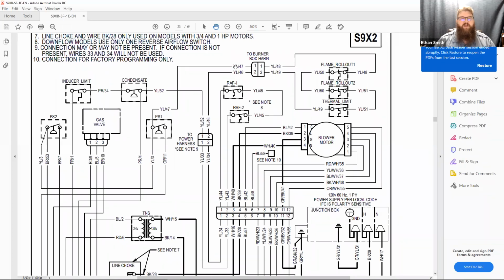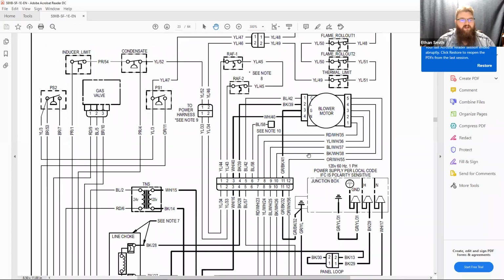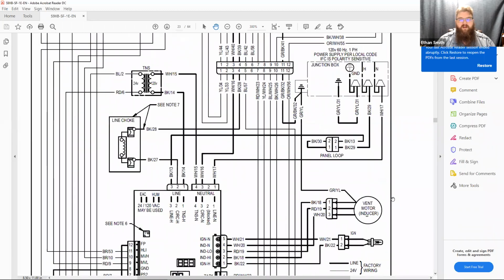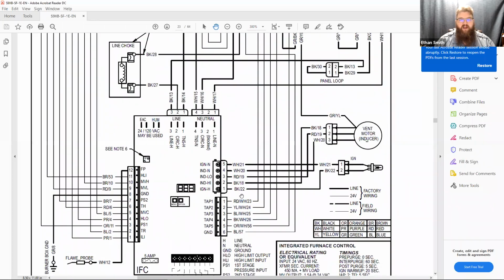Okay, so we can go out and we can check all of our switches, make sure they're all in the proper position. Okay, moving through the sequence of operation, we know that it's going to start my inducer at that point. So we can find my inducer motor on the wiring diagram. Here it is right here. Okay, if we look at the wiring diagram, it has my inducer neutral right here, and I have my inducer low speed right here. So we know that if all my switches are closed, it should be sending power out to my inducer.